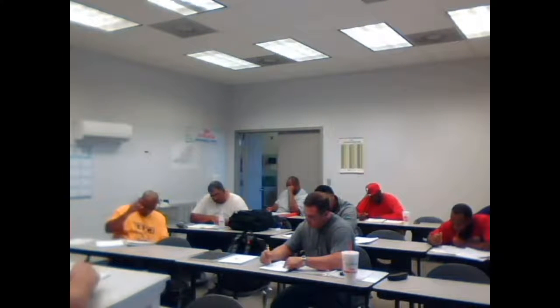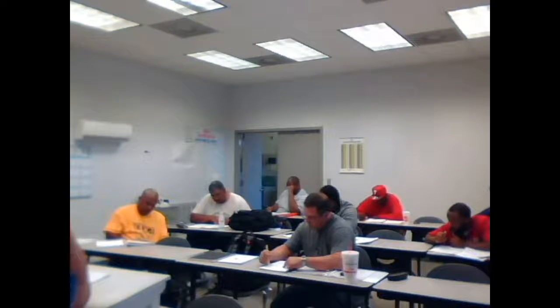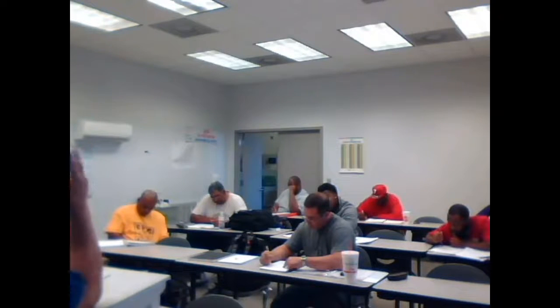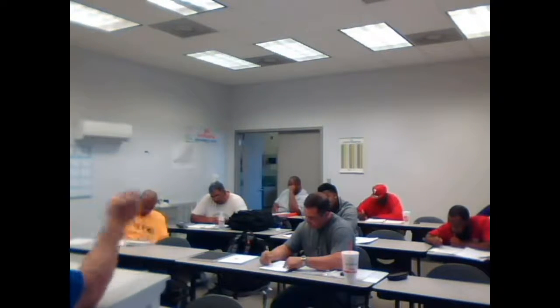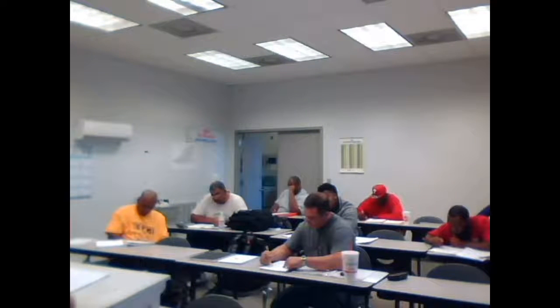So I'm going to go to my picture diagram below. Yes, sir. On that L2, we stop at the contactor. That's it. Yeah, so in the picture, I got you. That turns into teaching. Yeah, but we'll hit that later. Right now, we're just getting our L1, L2, and L3. So I go to L3. I'm going to need 3 wires. One's going to go straight across down to the contactor. That's one.